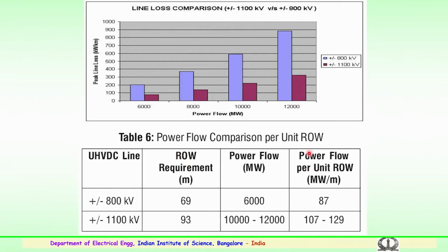So, the power flow comparison per unit right of way gives an idea here for the plus minus 800 kV ultra high voltage DC line and the 1100 kV line. The right of way requirement will be 69 meters in the case of 800 kV HVDC. In the case of 1100 it is 93 meters, whereas for 800 kV you can transmit around 6,000 megawatts, and the power flow per unit, that is megawatts per meter, is 87. But for 1100 kV you can transmit up to 12,000 megawatts, that is very important. So, double the power could be transmitted going from 800 to 1100 kV HVDC. That is one of the major benefits of going in for the higher UHV DC of 1100 kV, which is presently being thought about, and the studies are being conducted.